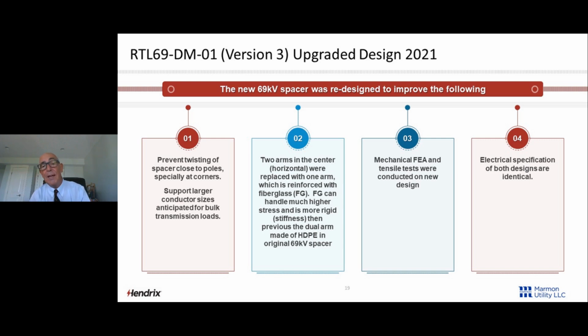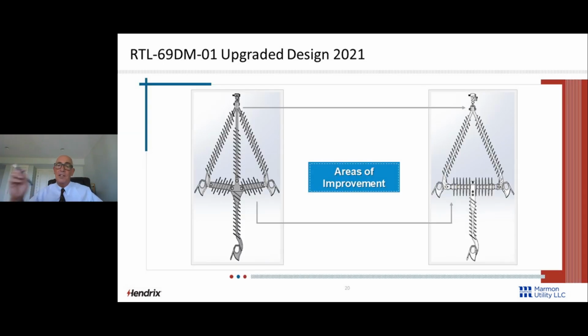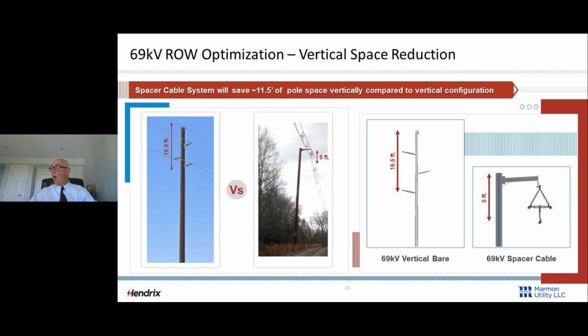We ran the mechanical FEA and tensile tests on the new design. We will do electrical tests at some point, which will apparently be a waste of money, since when you do the BIL and 60 Hertz withstand tests on a spacer, the only thing you're testing is the air. And we have those from the same dimensions, but in any case. Those are the areas of improvement. So you can see that center beam is really massively reinforced. I'm not going to show you the FEA, the finite element runs, but we increased that mechanical strength by a good 5x. So that's wonderful.